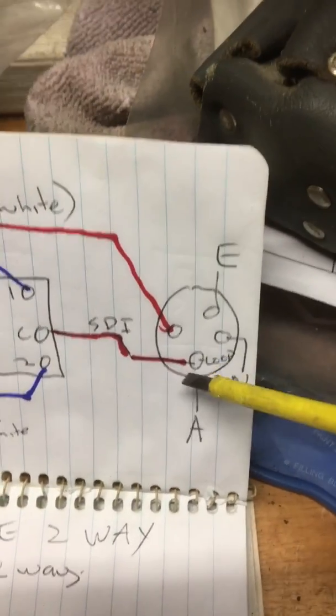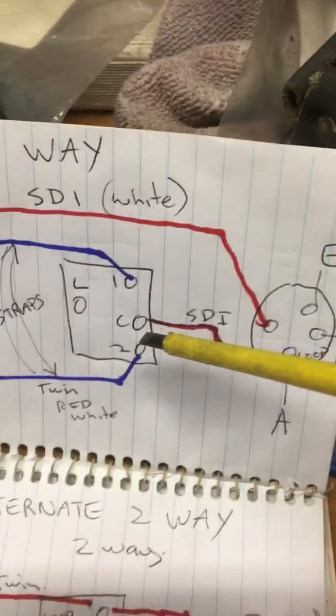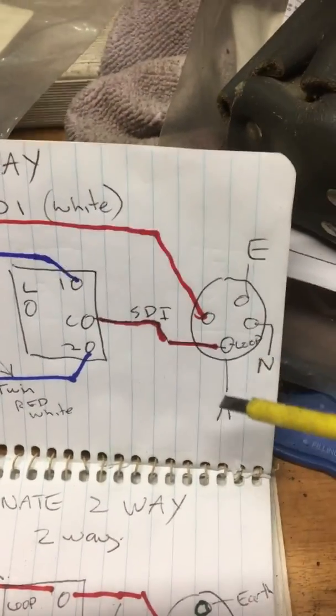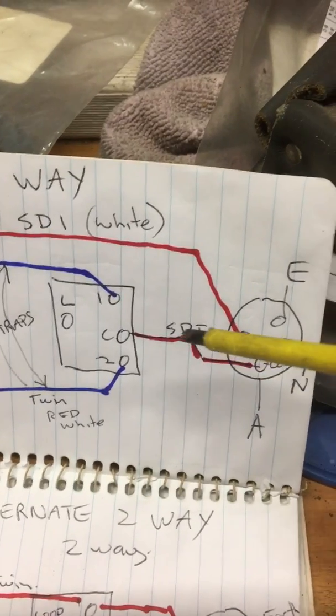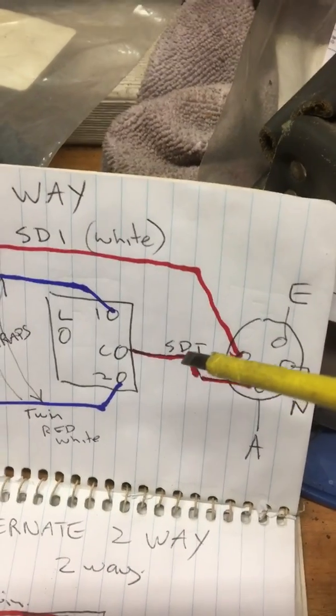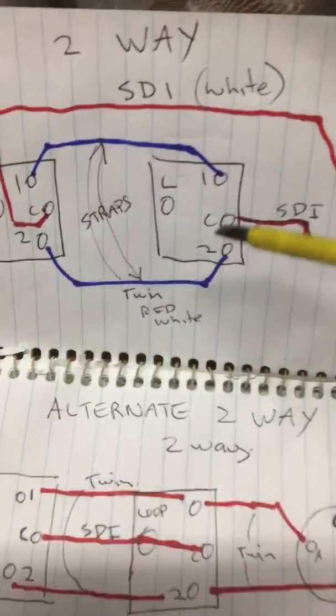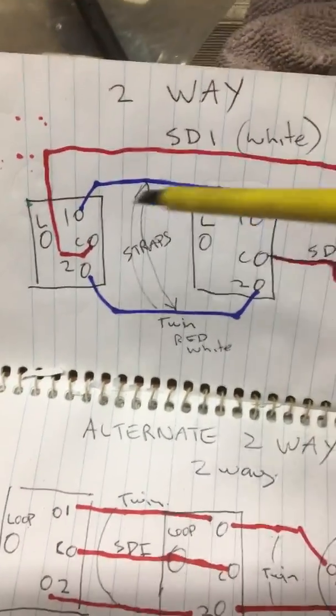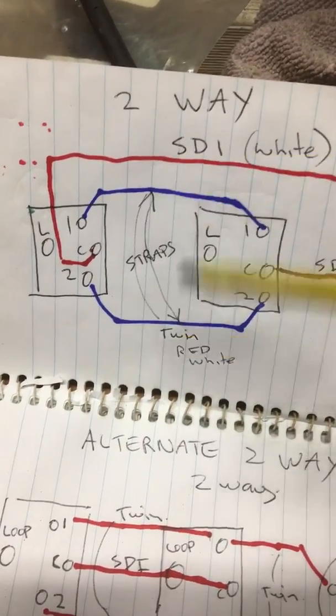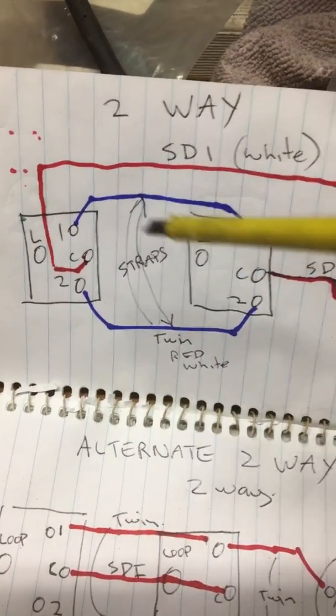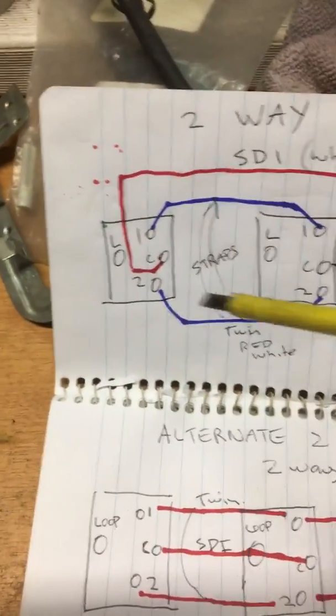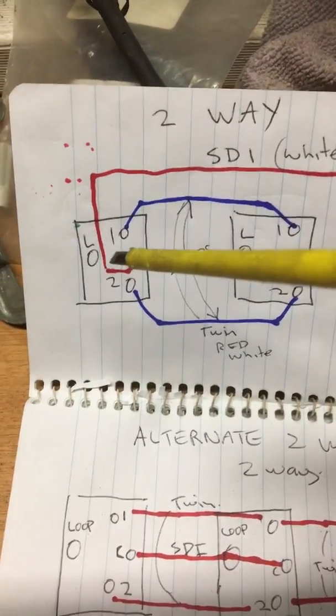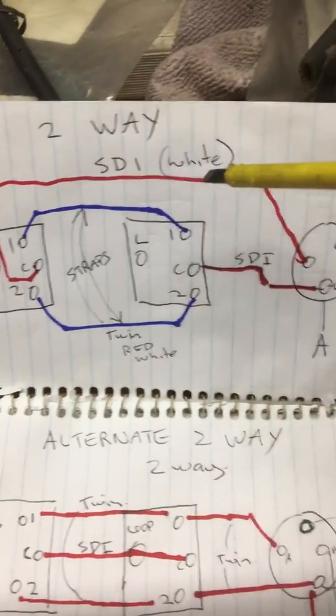From the switchboard loop to the switches via an SDI (single double insulated) into your common. Then from switch to switch is just twin, called straps, red and white. Then from the common of the second switch, just a single SDI back to your light terminal.